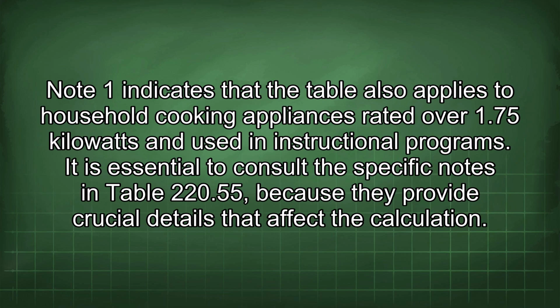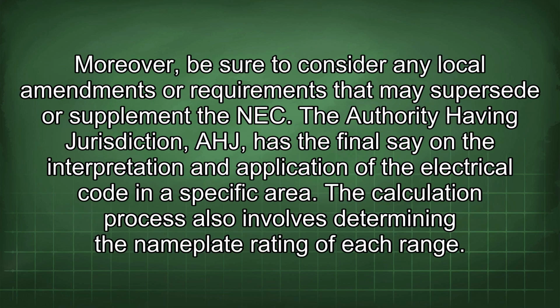Note 1 indicates that the table also applies to household cooking appliances rated over 1.75 kilowatts and used in instructional programs. It is essential to consult the specific notes in Table 220.55 because they provide crucial details that affect the calculation. Moreover, be sure to consider any local amendments or requirements that may supersede or supplement the NEC. The authority having jurisdiction, AHJ, has the final say on the interpretation and application of the electrical code in a specific area.